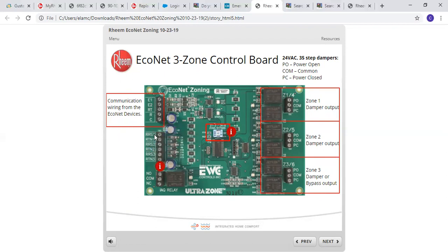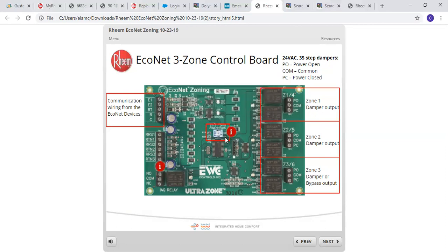This section here, the RR section, as well as the IAQ relay, are currently unused. You do have two dip switches here, so depending on what you're doing, you have to be aware of what you're setting up. If you're going to do a 2-zone system, or even a 2-zone with a bypass, those switches will be off. Generally speaking, they're going to be in the off position if you're using one board and not 2. If you do have to make changes on a 2-zone system, make sure you make the changes with the power off and then turn it back on so it'll accept it.